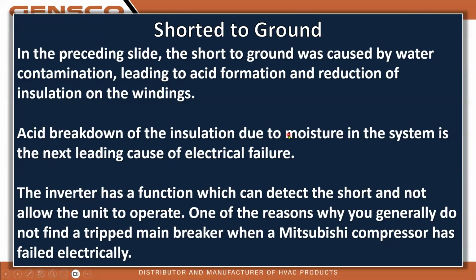And that preceding slide, the one that was pretty nasty, that was actually caused by water contamination. If moisture is in the system, it can lead to acid formation, and it will reduce the insulation value on the windings by taking the insulation off. Acid breakdown of the insulation due to moisture is the next leading cause of electrical failure outside of mechanical debris or damage causing it.